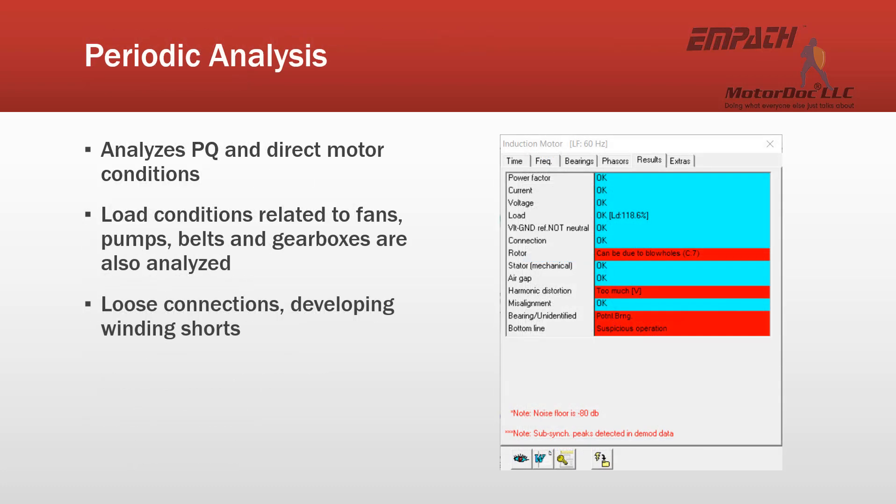The periodic analysis looks at not just the power quality and direct motor conditions, but also looks at load conditions related to fans, pumps, belts, gearboxes, and other related equipment. It also will identify loose connections, developing winding shorts, and other conditions that are detrimental to your system.